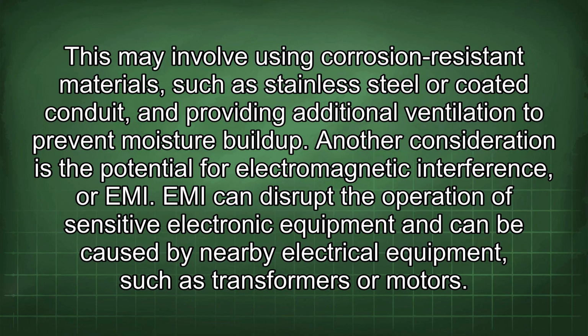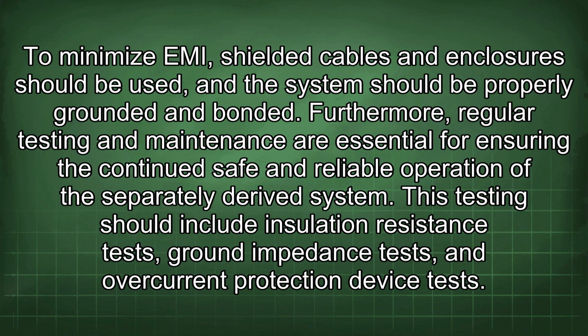Another consideration is the potential for electromagnetic interference, or EMI. EMI can disrupt the operation of sensitive electronic equipment and can be caused by nearby electrical equipment, such as transformers or motors. To minimize EMI, shielded cables and enclosures should be used, and the system should be properly grounded and bonded.